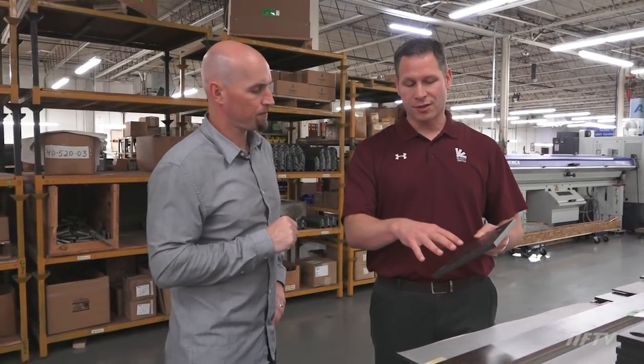And what's the purpose of this? So this is basically an insulating material, a high pressure laminate used to mount the electrical contacts on it. You have to have non-conductive material between the positions of the switch, so that's what this material does. It insulates between our connections on the switch.